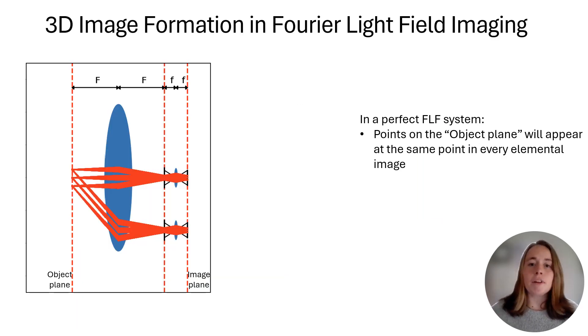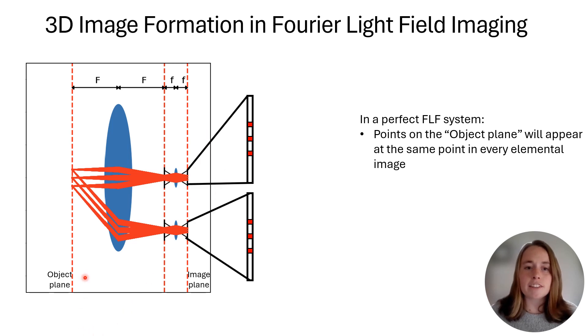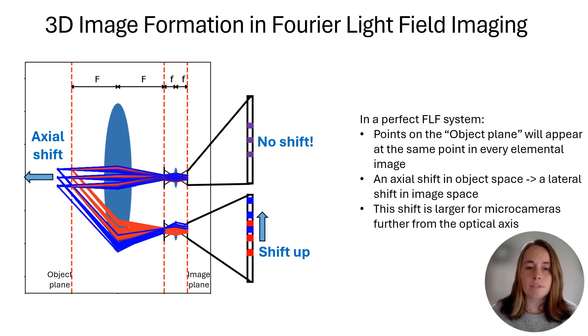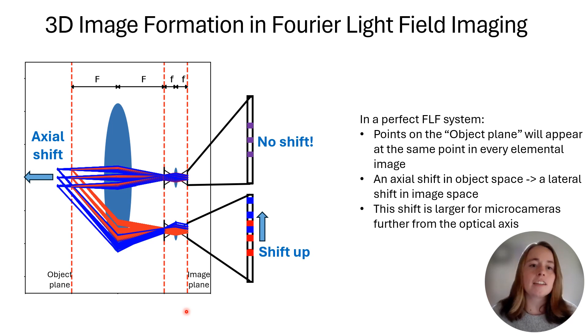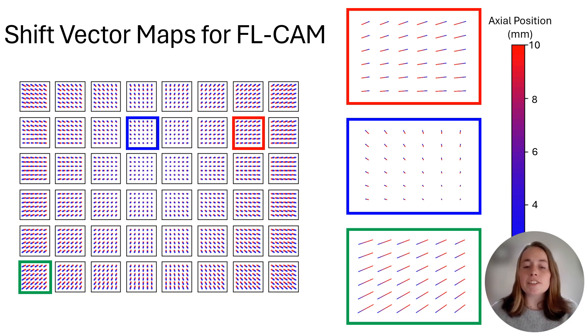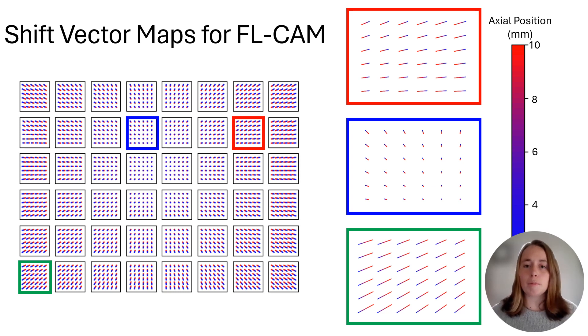Before I explain our 3D reconstruction algorithm, I want to return to this diagram and review how 3D information is encoded in a Fourier light field system. In a perfect system, points on the object plane will appear at the same point in every elemental image. Each of our micro cameras would theoretically form an identical image of a flat sample sitting on the object plane. But as a point in object space shifts axially, its image in each elemental image shifts laterally, and the magnitude of that shift varies according to how far the array lens is from the optical axis. The image of the point would not shift at all for a lens centered on the optical axis, whereas we see a large lateral shift for a lens sitting further out. We can calibrate the FL cam by measuring these shift vectors across the full field of view for each of our 48 cameras. Backward and forward projection between object and image space is achieved simply by shifting the pixels in our acquired images according to these vector maps.